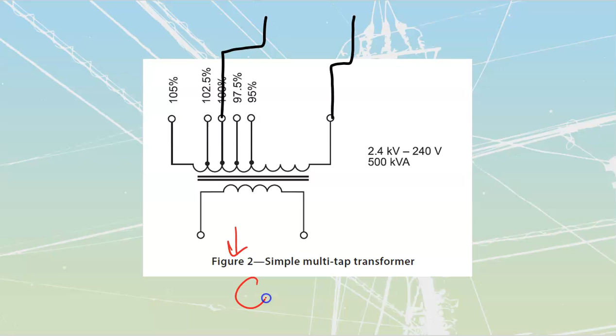Let's say that I am getting a reading of 220 volts out. If I'm getting 220 volts out and I know I should be at 240, all I need to do is find out what percent of my rated voltage that 220 is. So my actual over top of my rated is all I'm going to do.